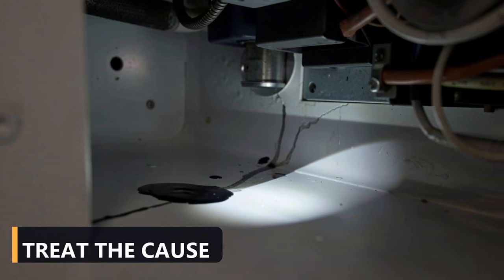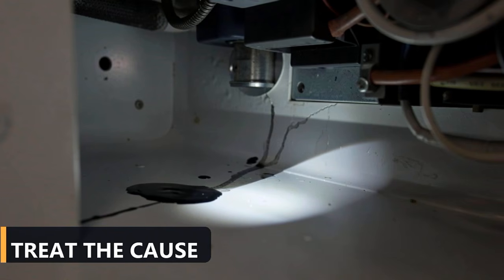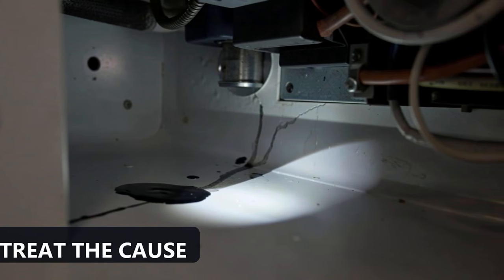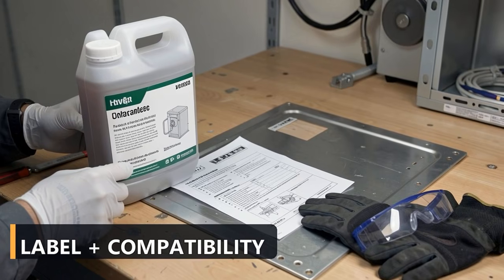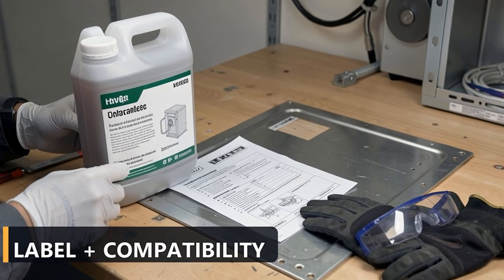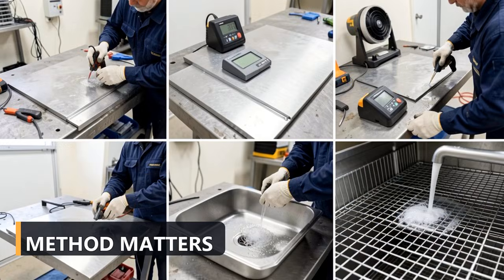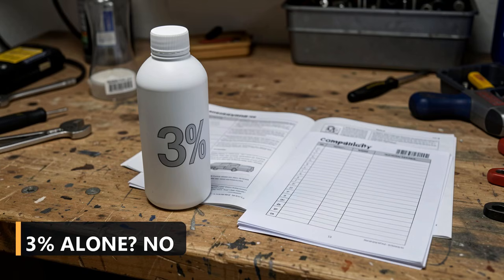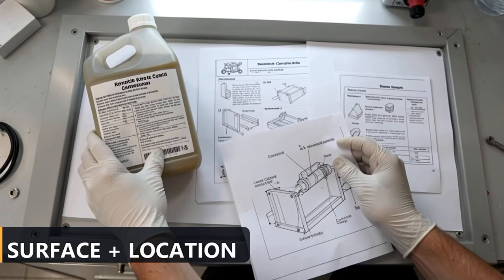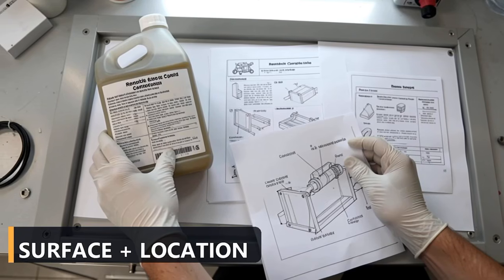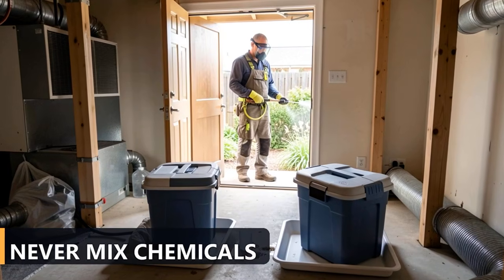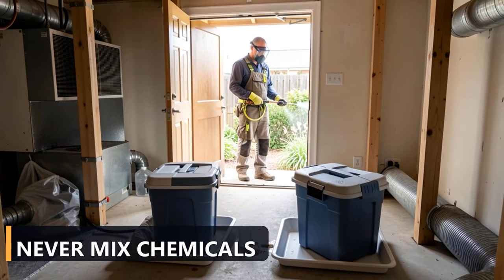Hydrogen peroxide can be an effective ingredient in properly labeled disinfectants and formulated HVAC cleaners. But concentration, surface compatibility, pre-cleaning, application method, contact time, rinsing, and drying all determine the result. An ordinary 3% bottle provides none of those answers by itself. Read the equipment manual and the cleaner label. Use only products approved for the intended surface and location. Wear the protection named on the label. Ventilate the work area, and never mix cleaning chemicals.